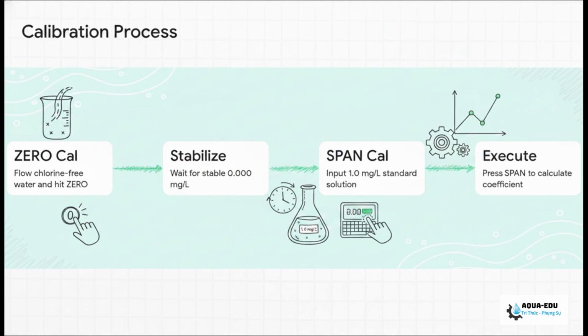First, run completely chlorine-free water, like pure RO or DI water, through the flow cell. Hit 0 on the touchscreen and just wait for the countdown to stabilize at exactly 0.000 milligrams per liter. Next, introduce a certified NIST traceable 1.0 milligram per liter standard solution. Input that value, press the green span button, and just let the processor automatically calculate the calibration coefficient. There's no need to dilute anything if it's within the unit's range.